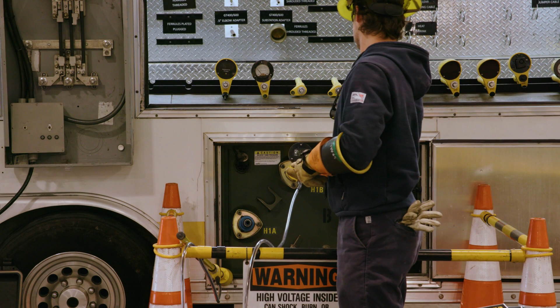Okay, what do you get? 3? Alright, so it's about, what, 0.3? Does it say 0.3? Yeah, 0.3. So there's a little bleed on that cable — do you hear that? If that cable right now was in wet grass, you'd see a higher reading, maybe 0.6, because of the wet grass. But here the concrete's pretty dry. There might be some steel in this concrete, I'm thinking, because normally with dry concrete we're getting closer to 1 or 2 or even 0. So I'm thinking there's some steel in this concrete, alright?